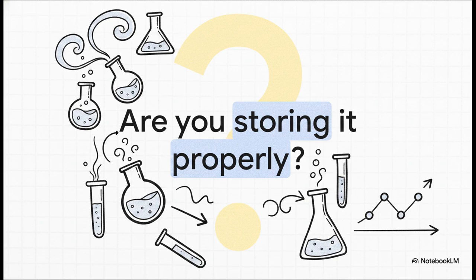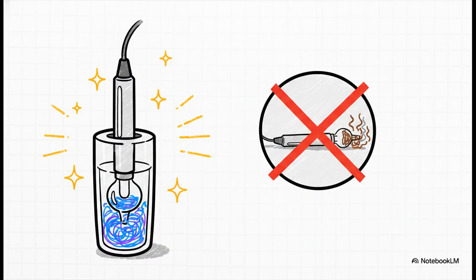Your measurement is recorded, but the science doesn't just stop because you wrote down a number. Are you actually storing your electrode properly? The answer is really simple, but it gets constantly overlooked. Never, ever leave the electrode out to dry in the ambient air. Always clean, rinse, and submerge your electrode in its dedicated KCl storage solution. Doing this ensures the delicate glass membrane remains perfectly hydrated and perfectly accurate for your next test.